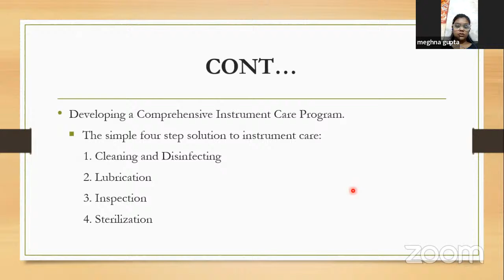Cleaning and disinfecting. Disinfection of soiled instruments not only helps to preserve the instruments themselves but also serves to protect the persons responsible for their transportation and cleaning. Wherever possible, instruments should be disinfected and cleaned immediately after use. Any soiling left to dry will make eventual cleaning far more difficult and could result in damage to the instrument.